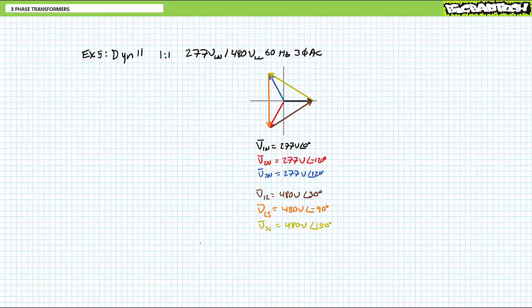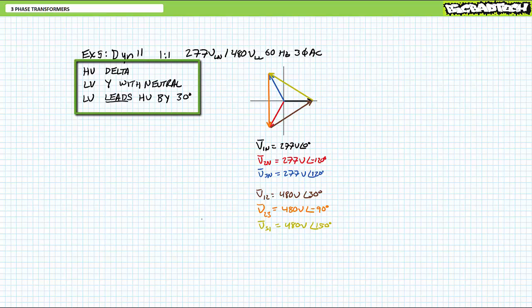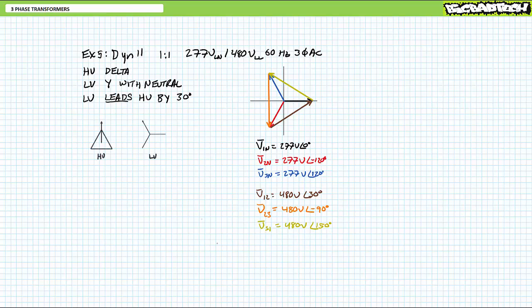Let's begin our analysis by dissecting the naming convention. The high voltage side is delta configured; the low voltage side is Y configured with a neutral; and the low voltage side leads the high voltage side by 30 degrees. For the displacement diagram, the high voltage side is delta configured, so you draw it as a triangle with a reference line-to-virtual-neutral voltage pointed straight up. Given the 11 o'clock designation, the Y-configured low voltage side's line-to-neutral leads the high voltage side's line-to-virtual-neutral by 30 degrees. You draw this as a regular Y configured phasor diagram, only tilted at 11 o'clock or positive 30 degrees.